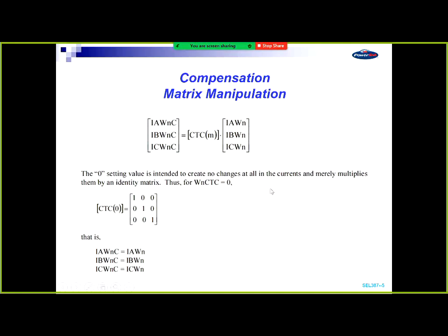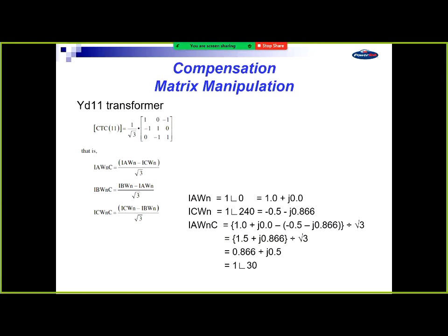What I've done here is the maths for one of them on one of the lines, and you can see how it works. So this is a YD11 transformer, so we select the 11 there. That's what we need to compensate for it. The IAWNC stands for A-phase winding compensated. So that's the formula. You've got that matrix there, you end up with a formula for your A-phase as being the A-phase current minus the C-phase current divided by √3. You work through the maths.